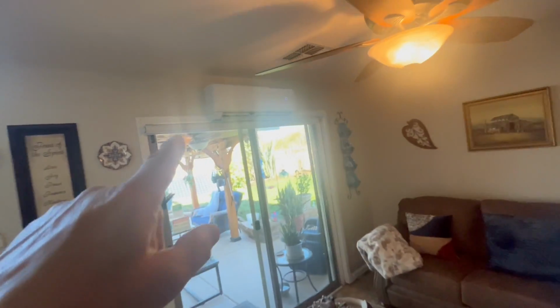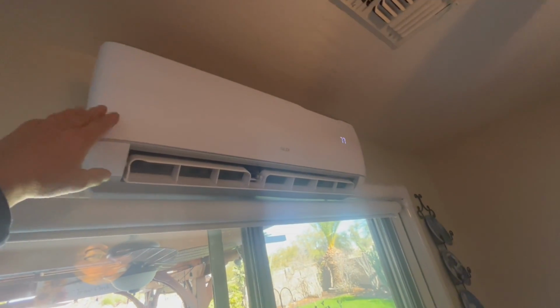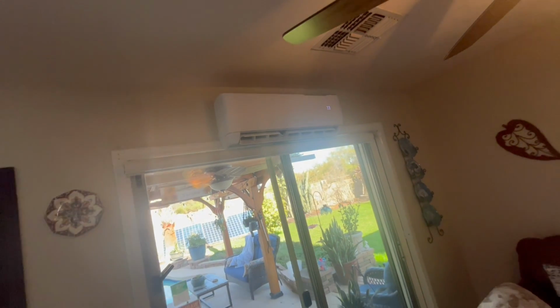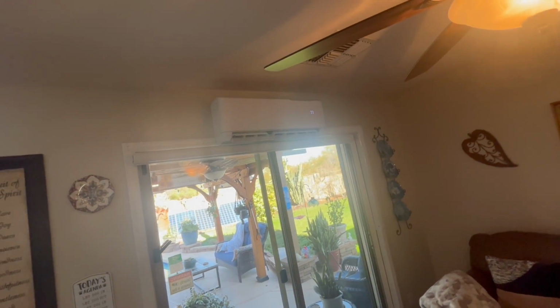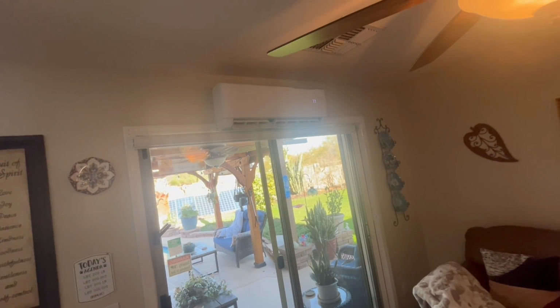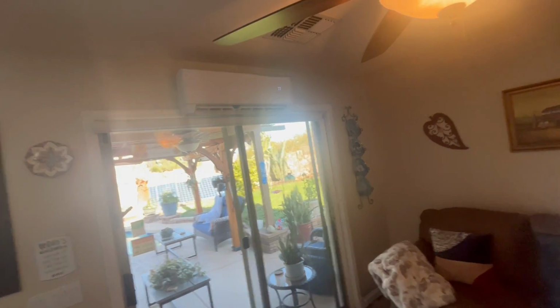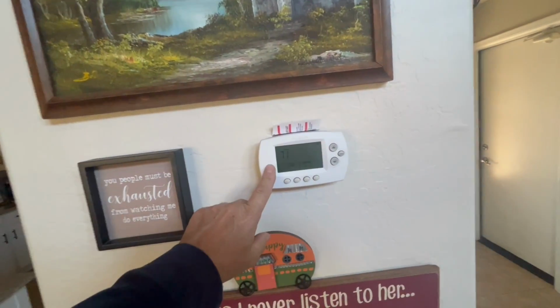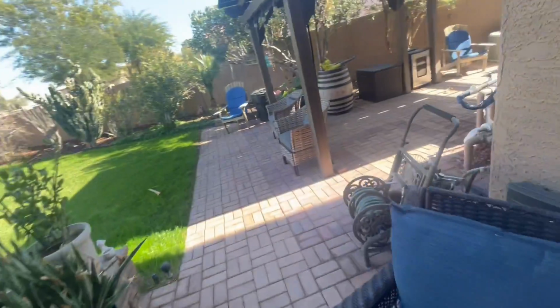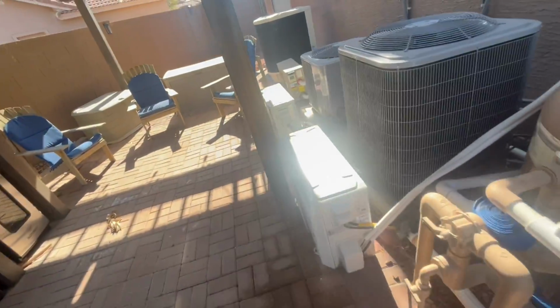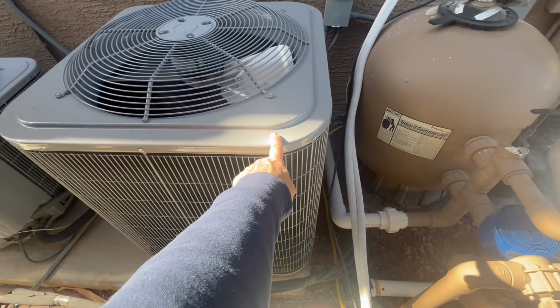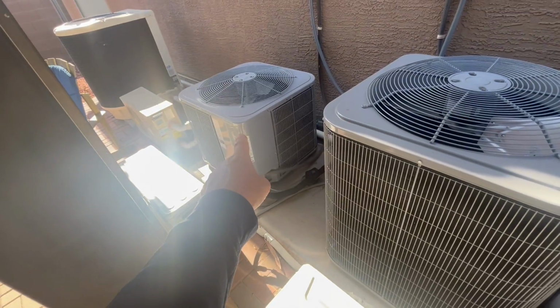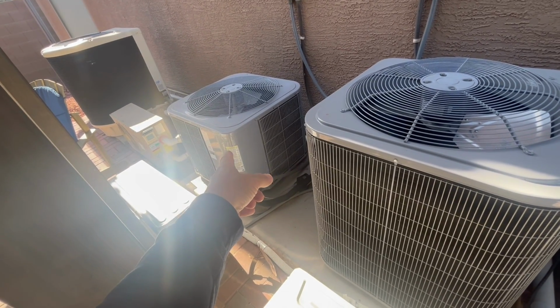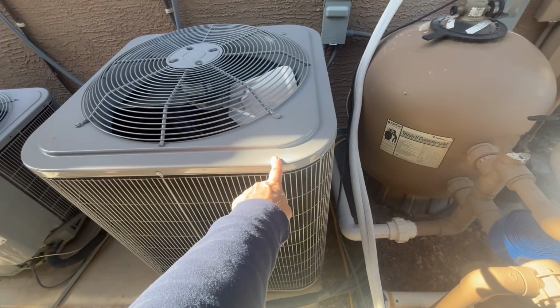Now, when these things start up, they start up at like 20 watts. There's no surge on them. It'll go like 20 watts, 40 watts, 45, 60, 80, 100, 120, about that fast. It's no surge. When this whole house air conditioner heat pump kicks on outside, it was calling for like 119 amps on the 4 ton and 78 amps on the 3.5. Now, this one was like 119 amps surge, and the 3.5 ton over there was like 78. That's down to like 20 to 22 startup amps. This one's like 34, 36.